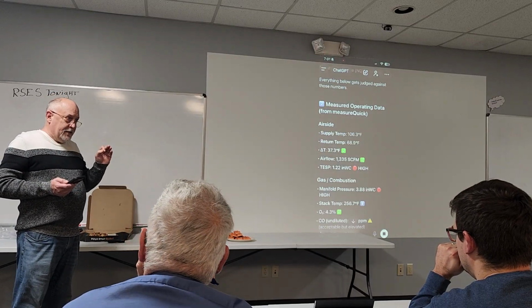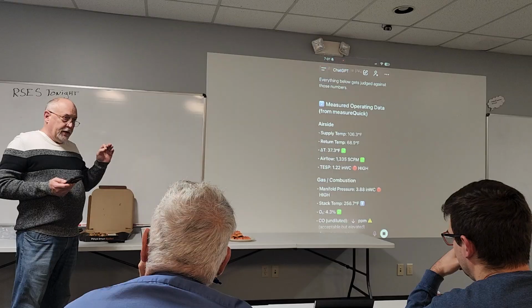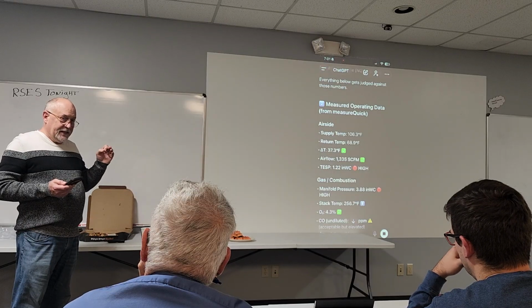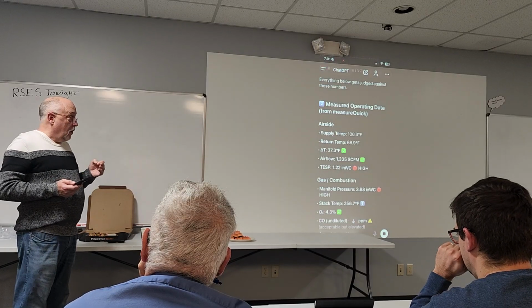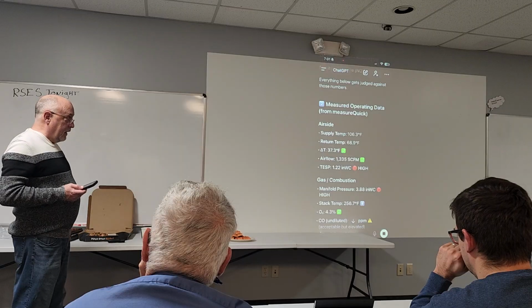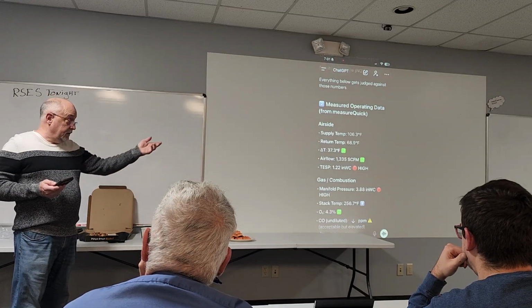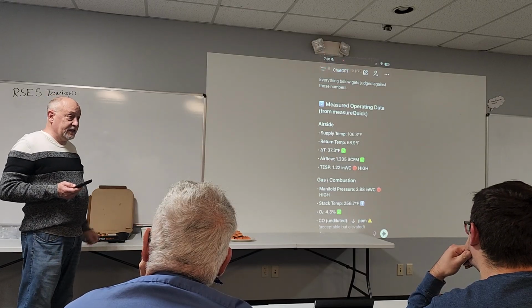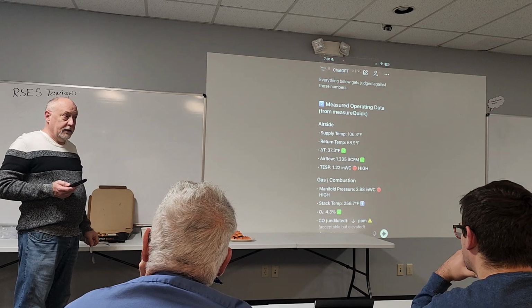Modern gas appliances typically require more airflow than air conditioning does. This is only a 60,000 BTU furnace. Why is that airflow so high? I mean, that's 3 tons of air across the 60,000 BTU furnace.